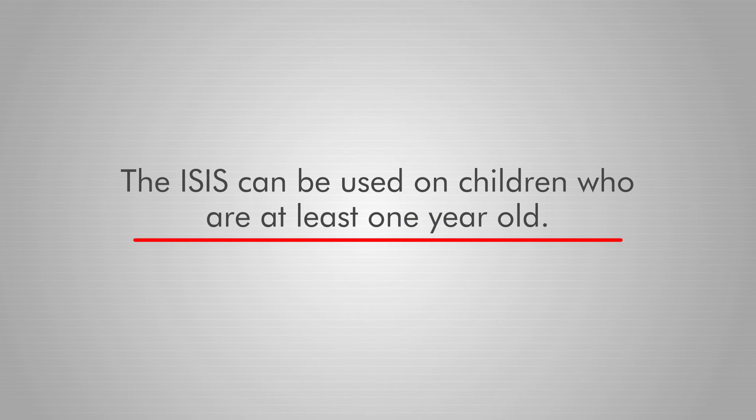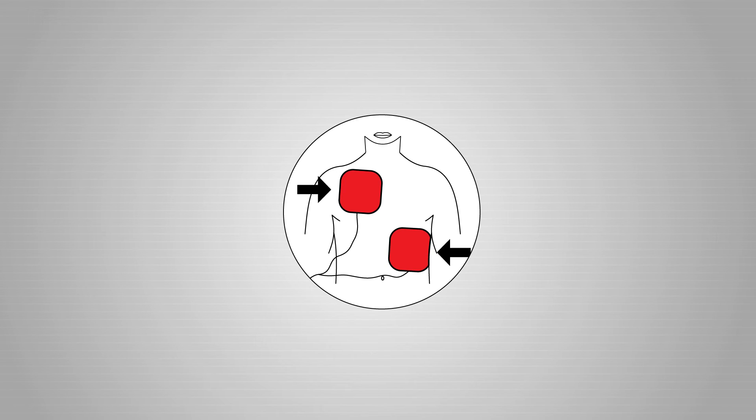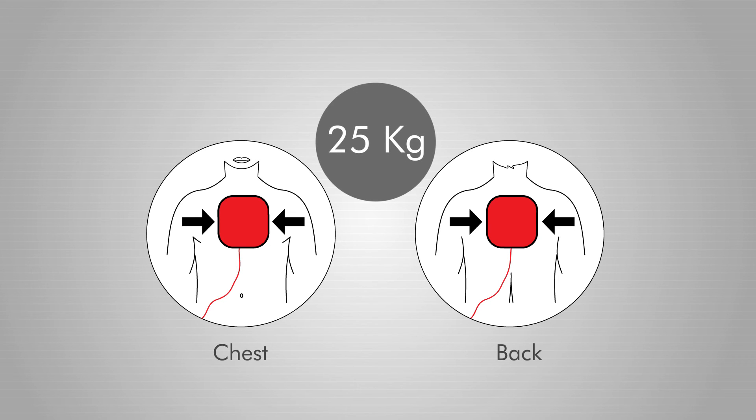The ISIS can be used on children who are at least one year old. The following precautions are to be taken when using this device on patients between one and eight years of age: use child-sized pads found in the Instamed dispenser. Should it not be possible to position the pads at least four centimeters apart, place one on the child's chest and the other on their back. This applies to patients weighing less than 25 kilograms as well.